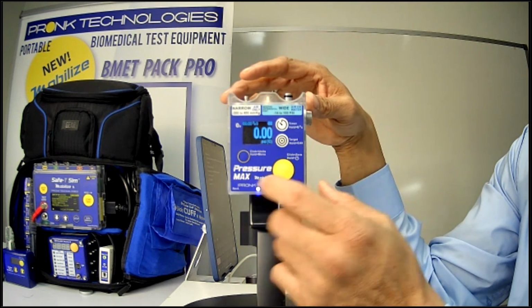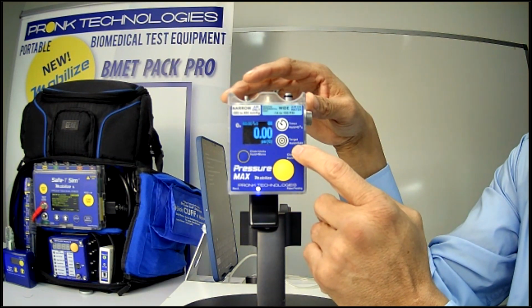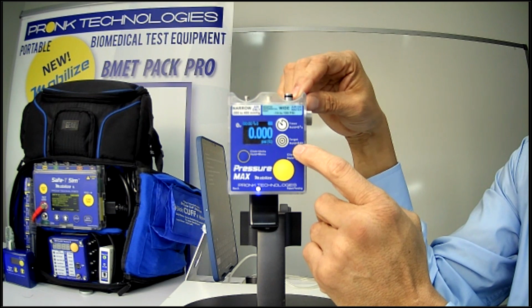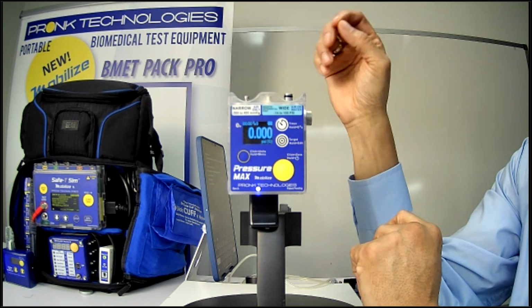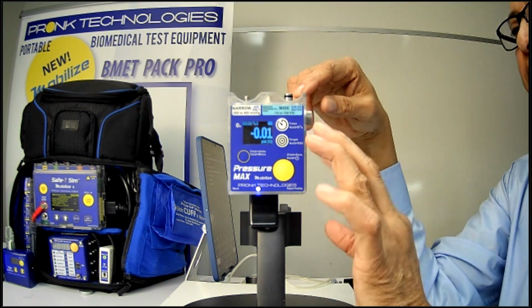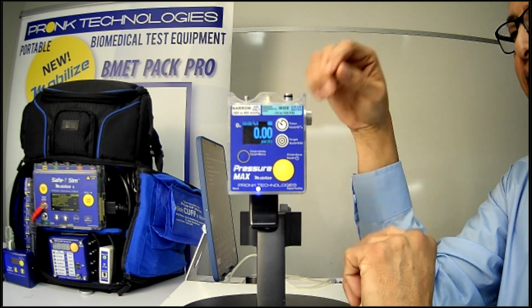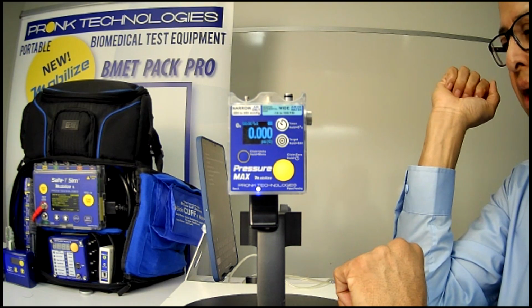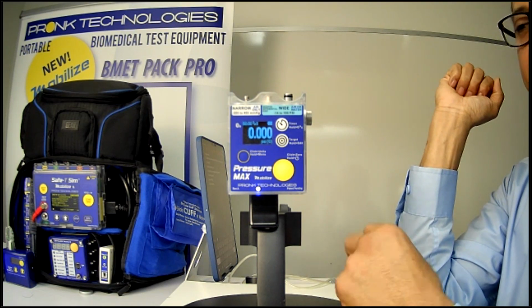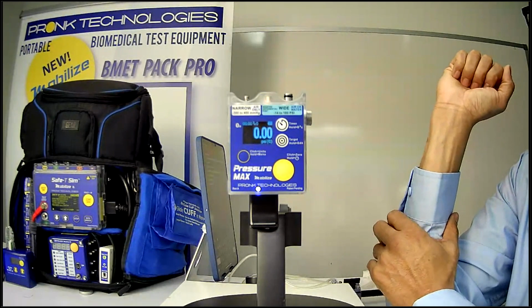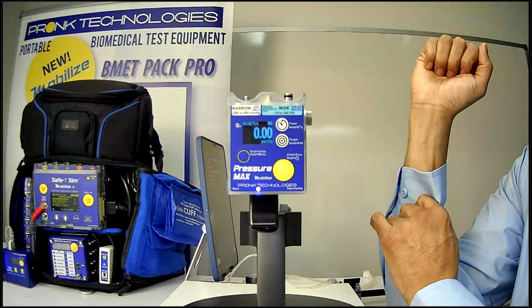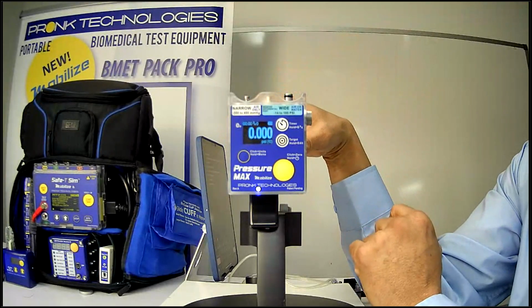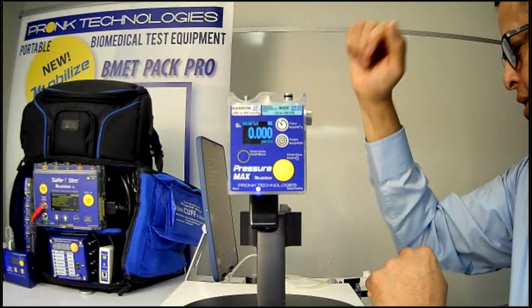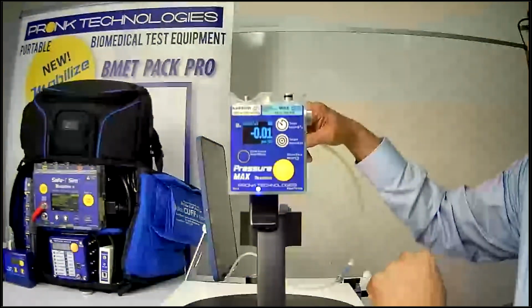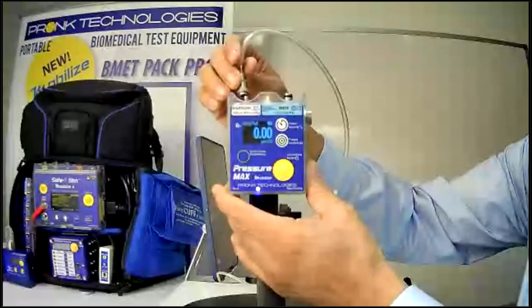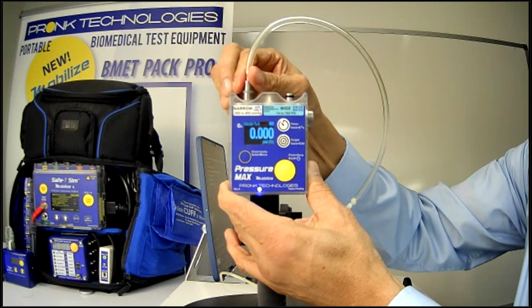So you have this button here that's also called target, which we'll go into in just a moment about setting targets and what that means. You're able to really program the unit to have specific pressure targets that you want to utilize. And you can define the pass-fail range of those targets, which can be really helpful, and we'll demonstrate that for you. To utilize it is very straightforward. Let's go ahead and just connect something to the narrow port so we can test that for you real quick, show you how that works.